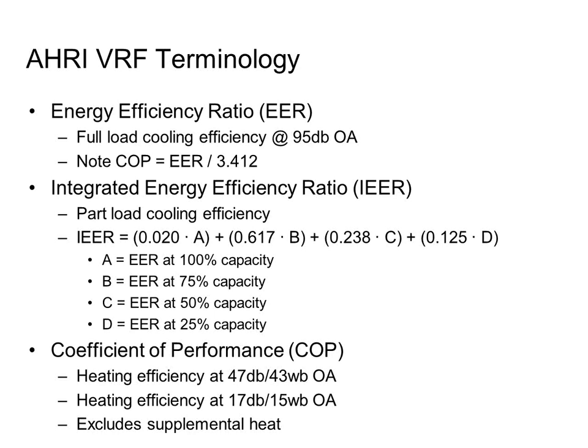The 17-degree number evolved into these rating systems decades ago because people recognized, well, I'm going to run my heat pump when it's less than 47, and because there's less heat available in the outdoor air, I'm going to get less capacity, so I need to know what's going to happen. So they just chopped 30 degrees off the rating number and did that testing point as well at 17 degrees, so you can kind of see that temperature dropping. Yeah, in a perfect world, they'd tell us the capacity difference and efficiency difference at every single outdoor condition, but that would be a lot of testing to do. So they give us 47 and they give us 17.